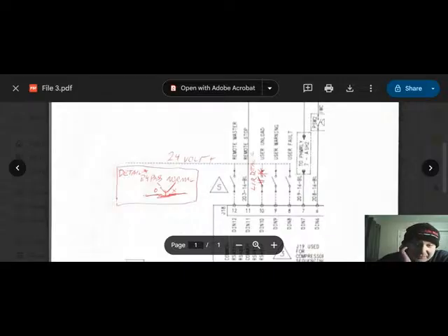Anytime you make any kind of a modification like this, I would definitely put some kind of a bypass switch in to easily defeat it. Obviously, being the installing technician, you would know, all I got to do is jumper this out or do this or that or the other, and everything's fine. But it may not be you that's coming back to work on it. It may be the end user needs to bypass whatever you've done here, and it's best to give them an easy way to do so.